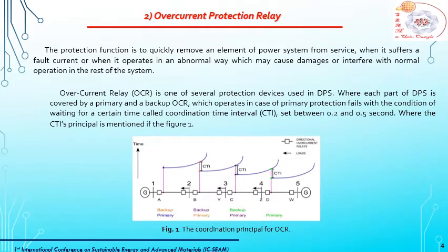In the second section of this work, we talked about the overcurrent protection relay, where the protection function is to quickly remove an element of a power system from service when it suffers fault current or when it operates in an abnormal way. The overcurrent relay is one of several protection devices used in DPS, where each part of DPS is covered by a primary and a backup overcurrent relay, and between them a coordination time interval, which its principle is mentioned in Figure 1.